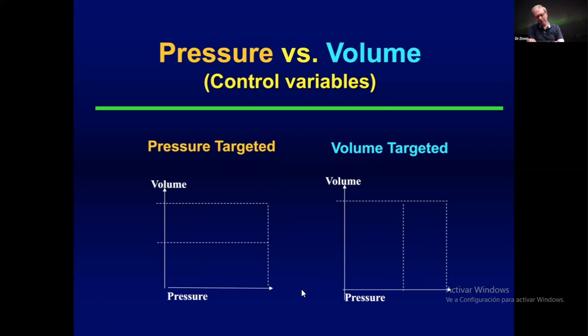When we look at the functional differences between pressure and volume targeting, depending on our control variable, this is a very interesting concept that we need to keep in mind. And that is, you can control one and the other will be variable, or vice versa. So in other words, here is our index breath during the pressure targeting. And you can see here that we are going to achieve a certain delivery of volume at a set pressure, depending upon the compliance of the lung. So if the lung is really stiff and we apply the same degree of pressure, we're not going to get as much volume delivery as if the lung were more compliant.